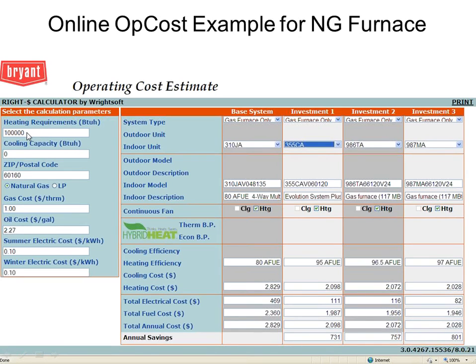And this is your load. This is not the size of your existing furnace, right? So if I have a 100,000 BTU furnace and it's 80%, my heating load is going to be 80,000 BTUs or perhaps even less. Once I do a load calc, I'll probably see that in most cases it's less. So up here you put the load of the house for heating and cooling. In this case, I left the cooling blank because I wanted to compare furnaces specifically for this presentation.